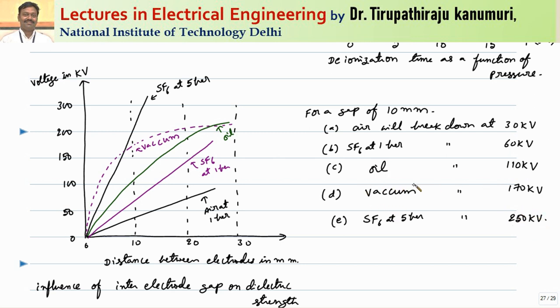Between oil and SF6 comes the vacuum circuit breaker. Initially, for small distances, the dielectric strength build-up in vacuum is far better than even SF6. But as the gap increases, vacuum circuit breakers are not as efficient as SF6. Generally, for 10 mm gap in vacuum, protection is up to 170 kV. For low voltage applications like 33 kV or 66 kV, the gap required is very less. Out of all circuit breakers, for low or medium voltages, vacuum needs the minimum gap, followed by SF6, then oil, then air. But for extreme high voltage above 220 kV, SF6 has the best performance.